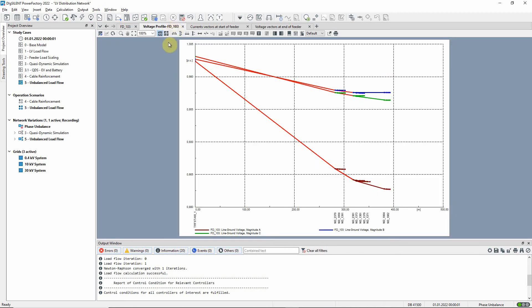The imbalance is reflected in the voltage profile. The voltage differences are very high, and some of the lines are loaded above their 80% upper limit, as indicated by the red coloring.